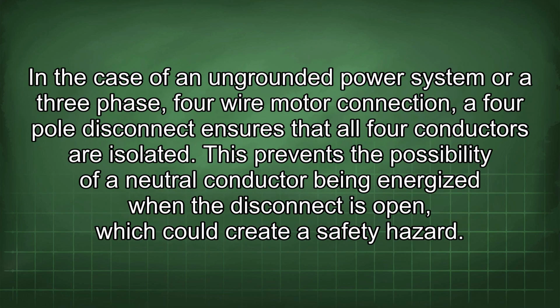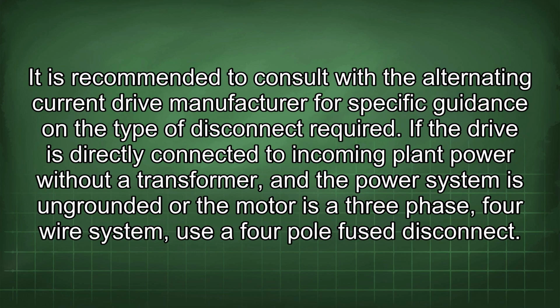In the case of an ungrounded power system or a 3-phase, 4-wire motor connection, a 4-pole disconnect ensures that all 4 conductors are isolated. This prevents the possibility of a neutral conductor being energized when the disconnect is open, which could create a safety hazard. It is recommended to consult with the alternating current drive manufacturer for specific guidance on the type of disconnect required.